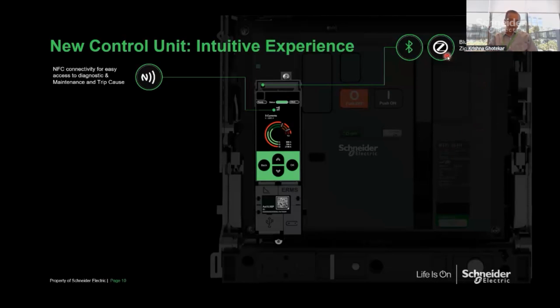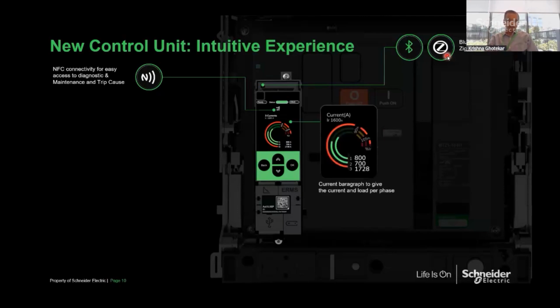And plus, for the first time in a circuit breaker, to make it a wireless communication, we have added Zigbee communication, which can directly connect to a PAS gateway. The trip unit now displays in a color display. The percentage loading for each phase comes in with color coding. That means if it is up to 90%, it's in green color. If it exceeds 90%, that means it's a pre-overload. From 90 to 100 it's an amber color, and then more than 100% goes into the red color.